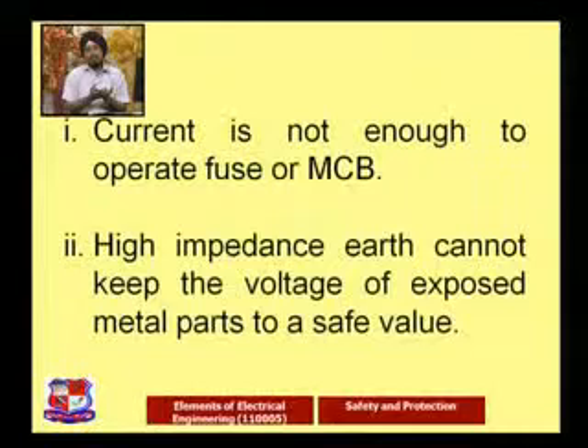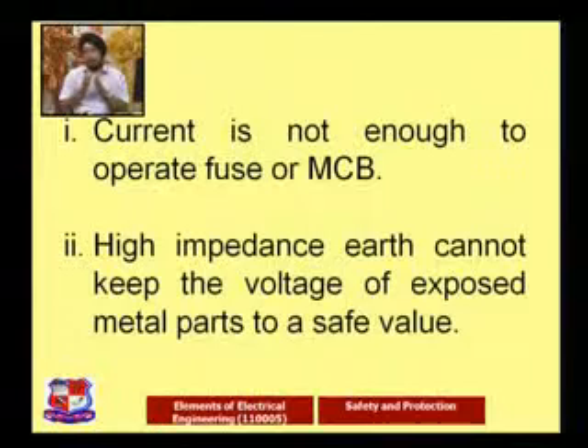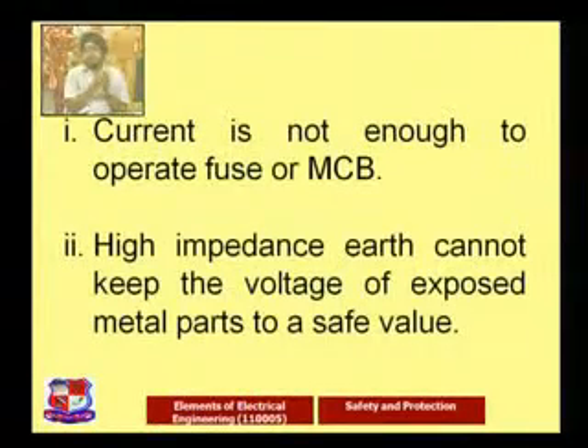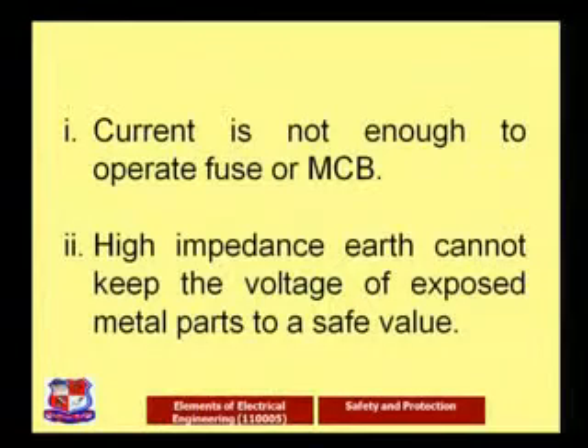The first is that the current is not enough to operate the fuse or MCB. A small amount of current is going through the earth, but it may not be enough to operate the protective devices we have discussed up to now, that is the fuse and MCB. So in that case the earthing or ELCB becomes very important. The second cause is high impedance. If the circuit has high impedance, the safe value of body earthing will not be achieved with respect to the device, and a fault will occur. The human working at that equipment or circuitry is going to have a problem.